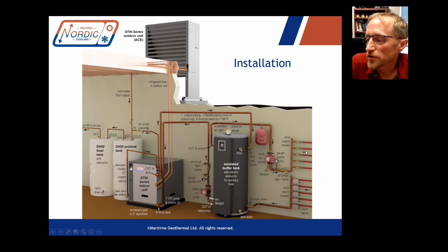And then your heating and cooling zones, instead of talking to the heat pump, are going to be either opening a zone valve and/or starting a zone circulation pump, which is going to demand water from that buffer tank. On the other side here, we have the domestic tanks we were talking about earlier. So the desuperheater, these small 1/2-inch connections on top, is heating a domestic water preheat tank, which can just be a normal, inexpensive water tank without the electric elements connected. And in the case that it doesn't heat the water all the way, there's a final water heater, which is usually an electric tank, or it can also be an instantaneous heater of some sort.